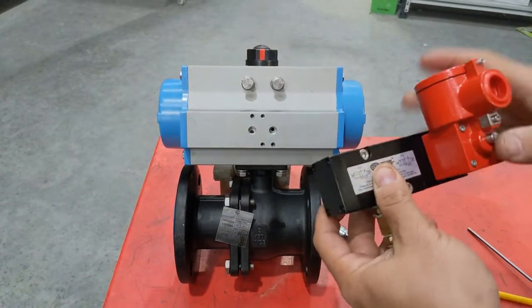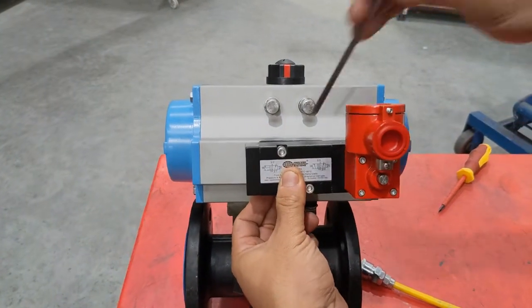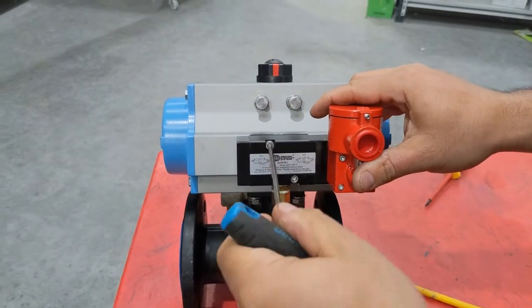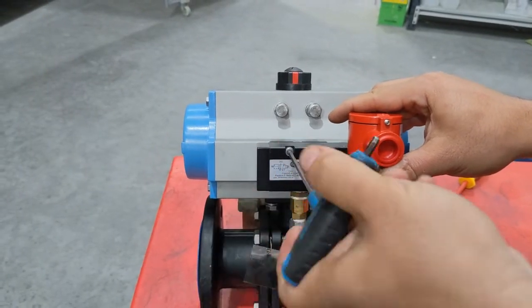Put the socket set screws through and put it over the Namur interface. Make sure the o-rings are on the adapter plate and tighten them onto the front of the valve. This will hold the 5/2 valve onto the face of the actuator and use the o-ring seal between the two faces.